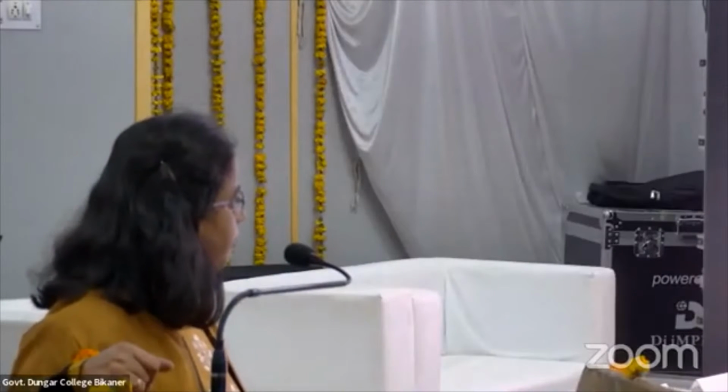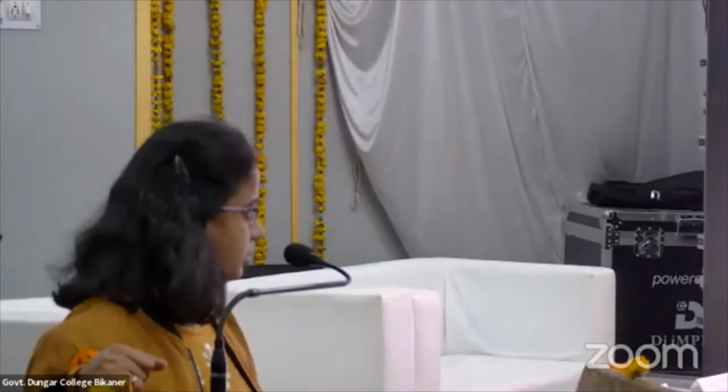So my presentation is about evaluation of out-of-field dose associated with flattened and unflattened clinical X-ray beams using MOSFET detectors. This is a preliminary study I have carried out in the clinical medical linear accelerator in our radiotherapy department. The purpose of the study is that, as we know, many modern technologies have come up in delivering radiotherapy treatment and also in the treatment planning system. But this improved conformity or modern technology has still not mitigated the dose to the out-of-field organs. So the physicists are trying to find out how to reduce the dose to out-of-field organs.